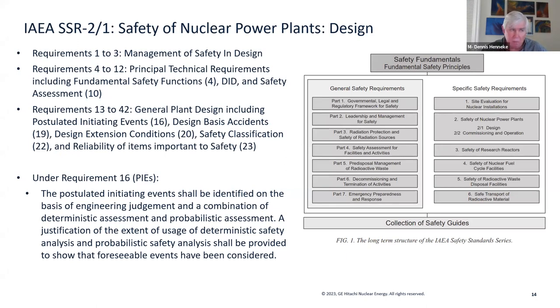The shall statement says you have to use PSA. In fact, SSR 2-1 says for an advanced plant design, you shall perform a PSA. The extent of use of that in developing your postulated initiating events, for updating your deterministic safety analysis, the performance of safety classification, and so on, is left to justification. In other words, you can go very much risk-informed, or you can do the PSA more on what we've referred to as a confirmation basis later on, or you can be somewhere in between.